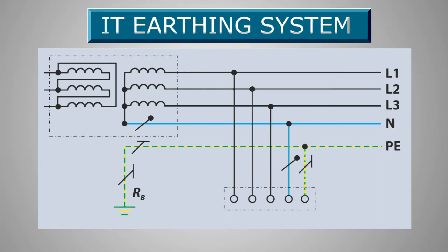The IT earthing system: the distribution system does not have any connections to earth, or it has only a high-impedance connection. The basic feature of the IT earthing system is that in the event of a fault between phases and earth, the system can continue to operate without interruption. Such a fault is referred to as a first fault. Thus, usual earthing protection is not effective for this system, and this type is not meant for consumer power supply. The IT earthing system is used for power distribution systems such as substations or generators.